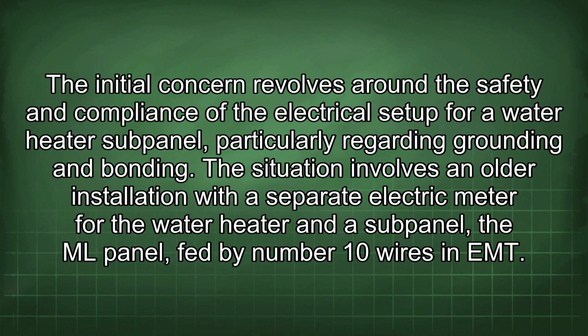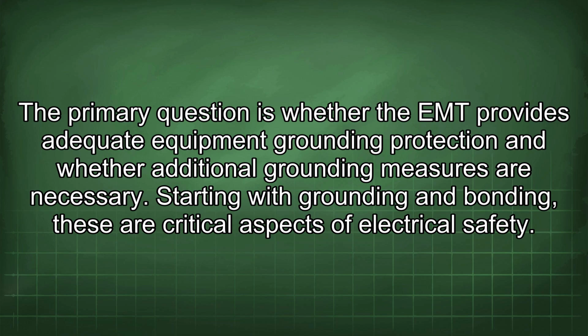The situation involves an older installation with a separate electric meter for the water heater and a subpanel, the ML panel, fed by number 10 wires in EMT. The primary question is whether the EMT provides adequate equipment grounding protection and whether additional grounding measures are necessary.